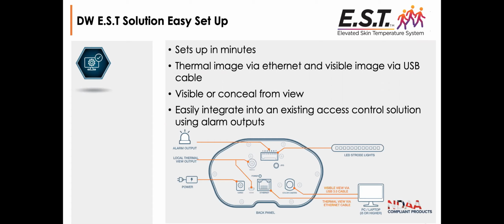The thermal image is connected via that Ethernet connection, as I mentioned, while the visible image is connected via the USB cable. So there's a 3.0 USB connection that's making that. It's going to direct connect to that PC. You can take the camera and mount it. We do provide the tripods in the kit, but if you wanted to wall or ceiling mount it, it's a universal mounting type device that you can attach to.